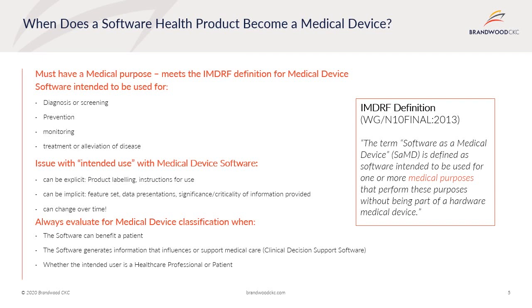The challenges of medical device software is that the intended use of claims may be explicit — that is, within the product labeling or instructions for use — or they may also be implicit, within the feature set, data presentations, expected or known use in the field, and the significance of the information provided. Also, software can change over time. The quick pace of software development means that with the introduction of new features, the intended use of claims may be broadened and hence impact the regulatory status.